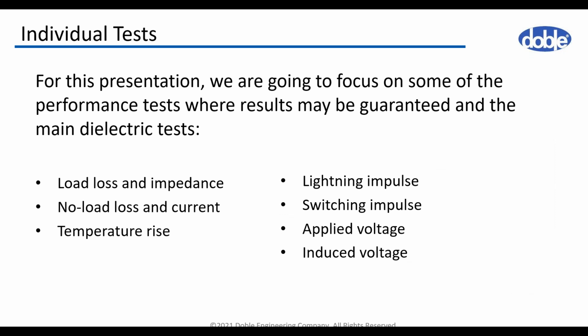For this presentation, we will be focusing on some of the performance tests, like no load loss and impedance, load loss and no load loss and current, load loss and impedance, and temperature rise test. The results for these tests are very frequently guaranteed values. We will also speak about some dielectric tests, like lightning impulse, switching impulse, applied voltage, and induced voltage test.